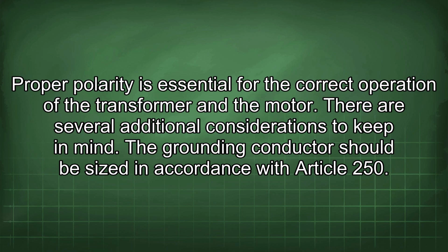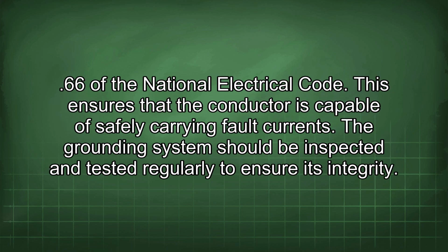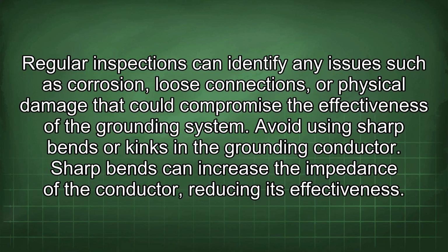There are several additional considerations to keep in mind. The grounding conductor should be sized in accordance with Article 250.66 of the National Electrical Code. This ensures that the conductor is capable of safely carrying fault currents. The grounding system should be inspected and tested regularly to ensure its integrity. Regular inspections can identify any issues such as corrosion, loose connections, or physical damage that could compromise the effectiveness of the grounding system. Avoid using sharp bends or kinks in the grounding conductor. Sharp bends can increase the impedance of the conductor, reducing its effectiveness.